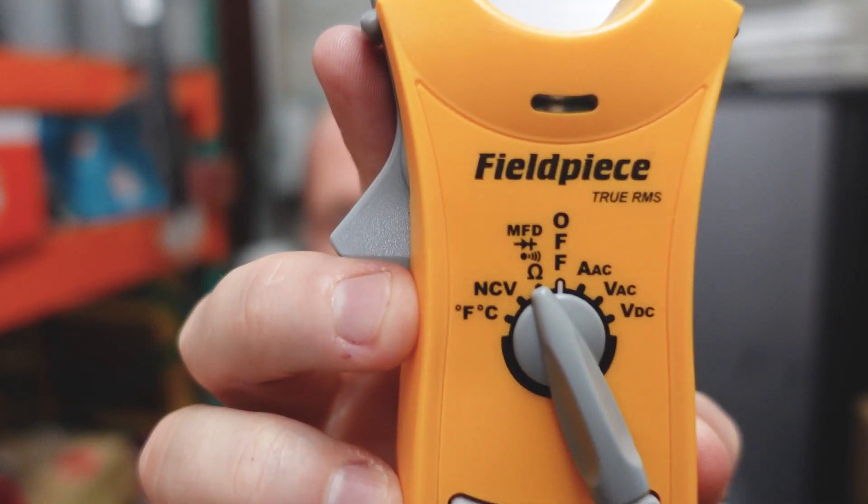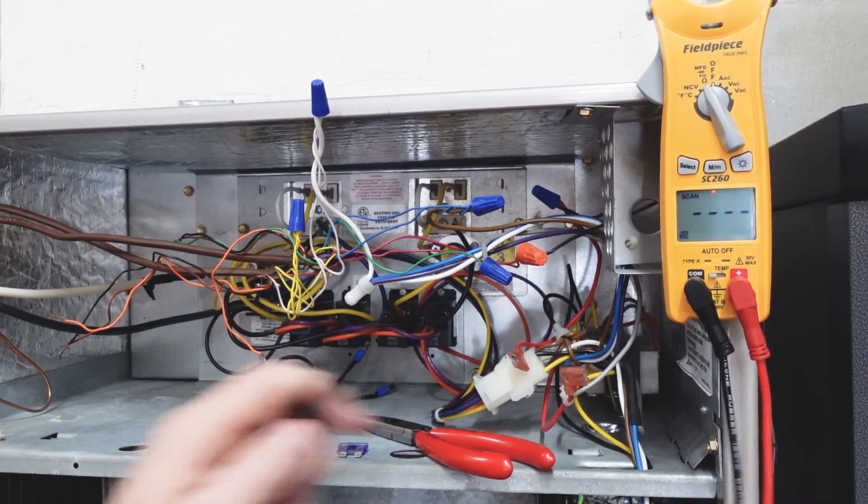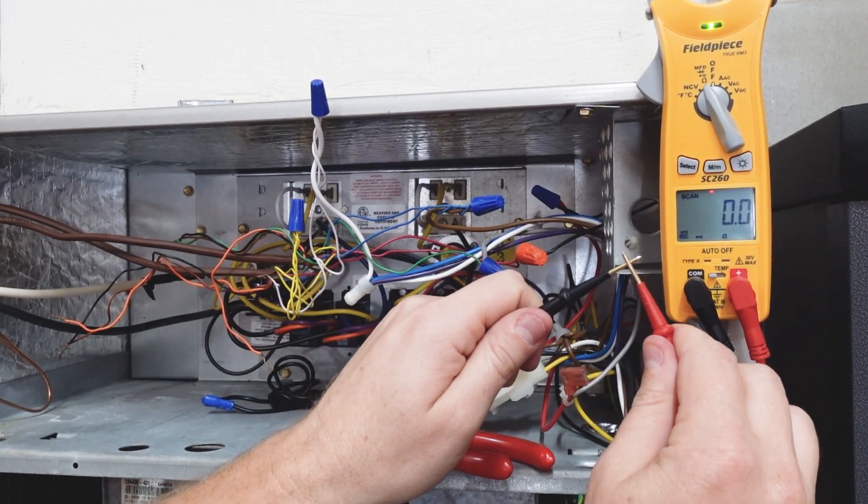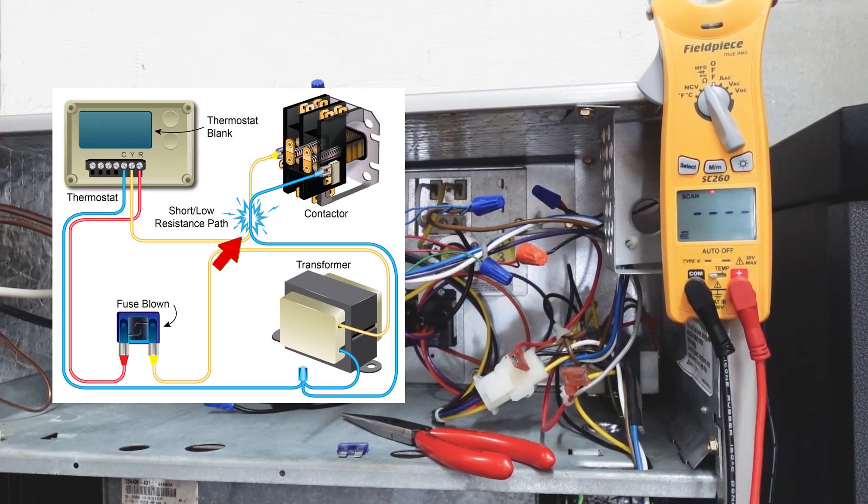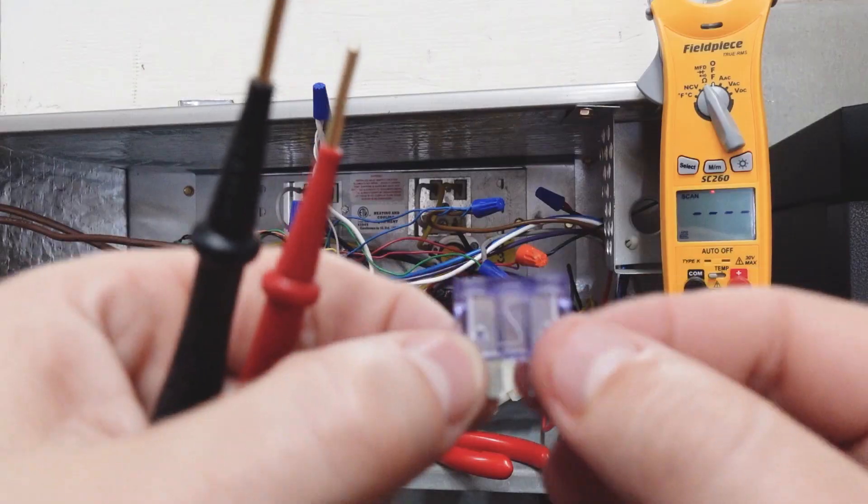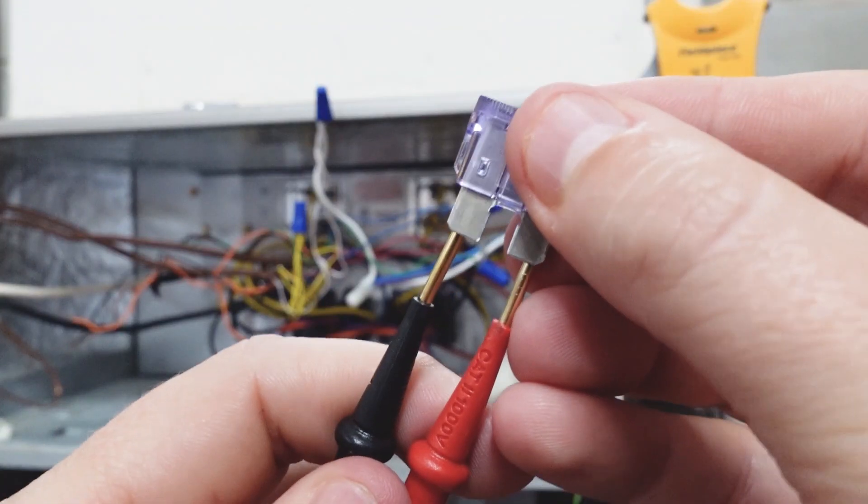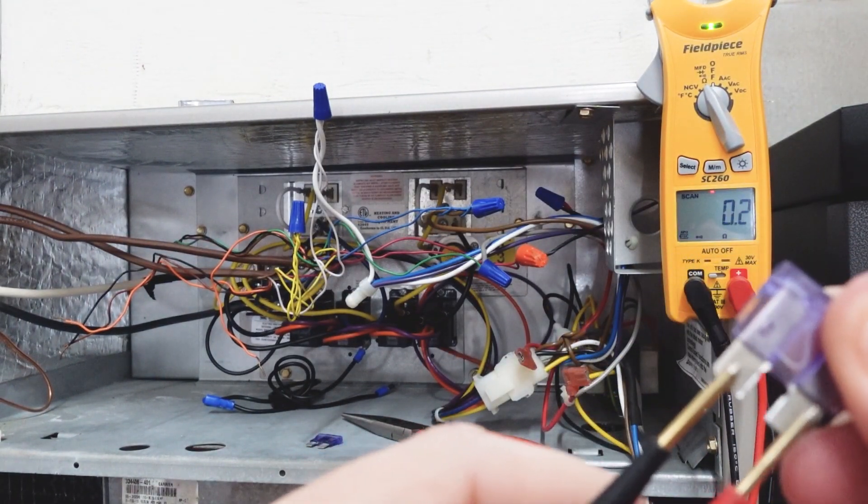These two spades are our connection points. So in order to test it, we put our meter onto the ohm scale. Specifically, we're measuring for continuity. Continuity means that there's a path, a path being a very, very low ohm or very low resistance connection with a fuse that does have a proper path and is not blown. We will ring out with continuity because we have a very low ohm path.